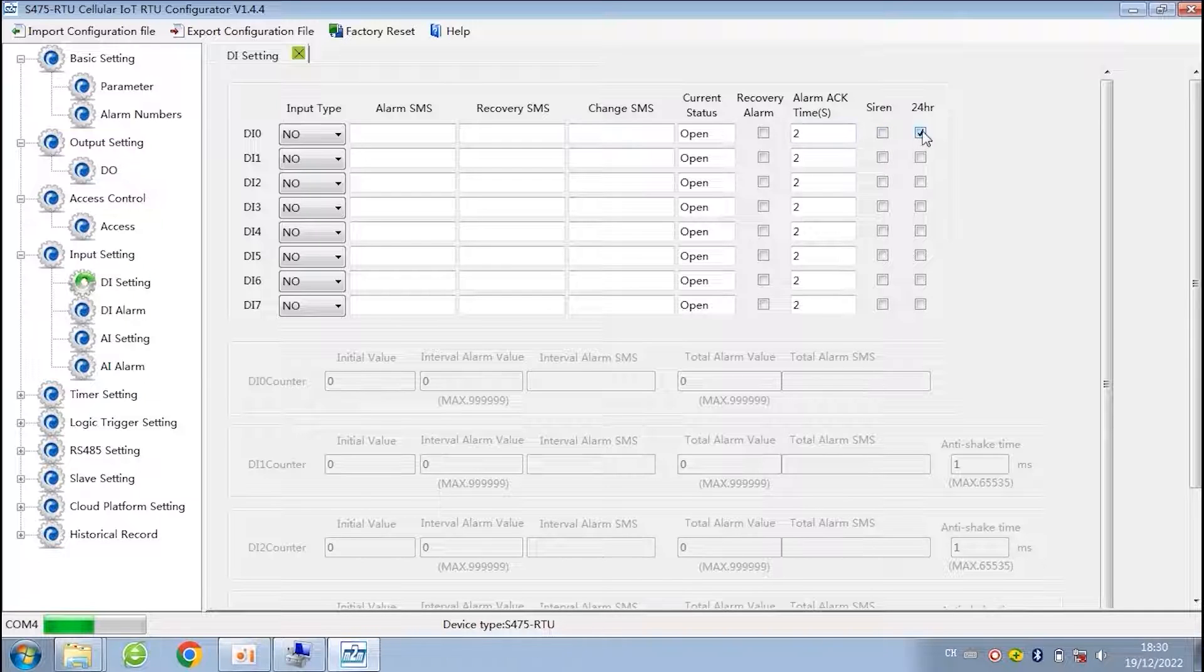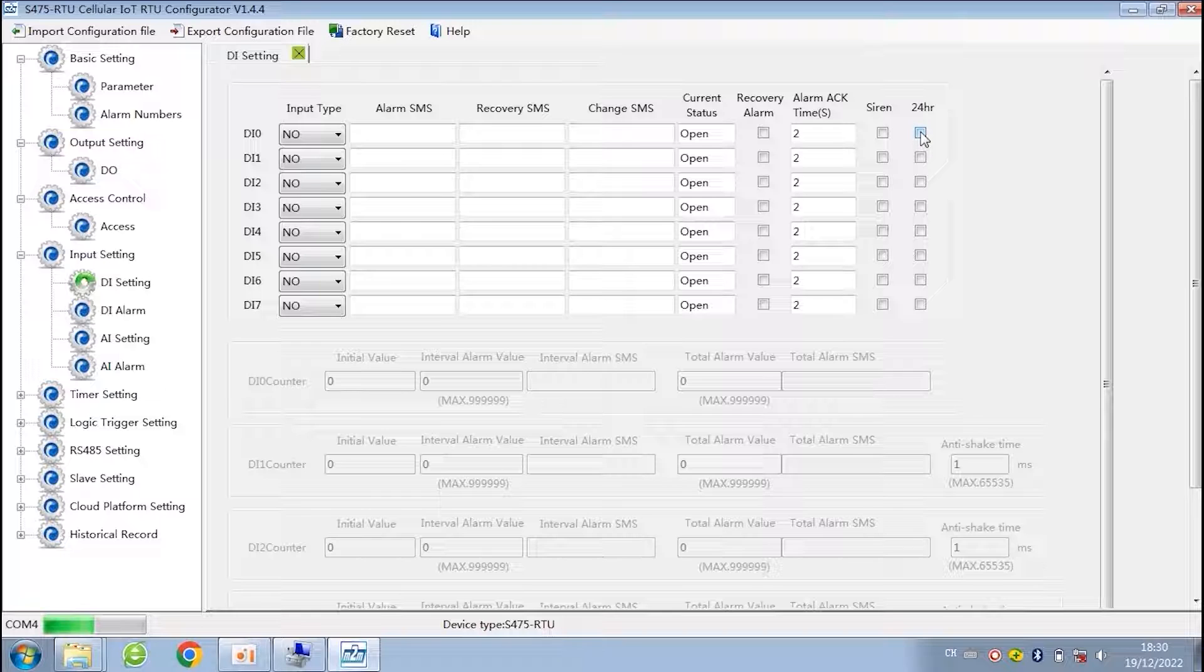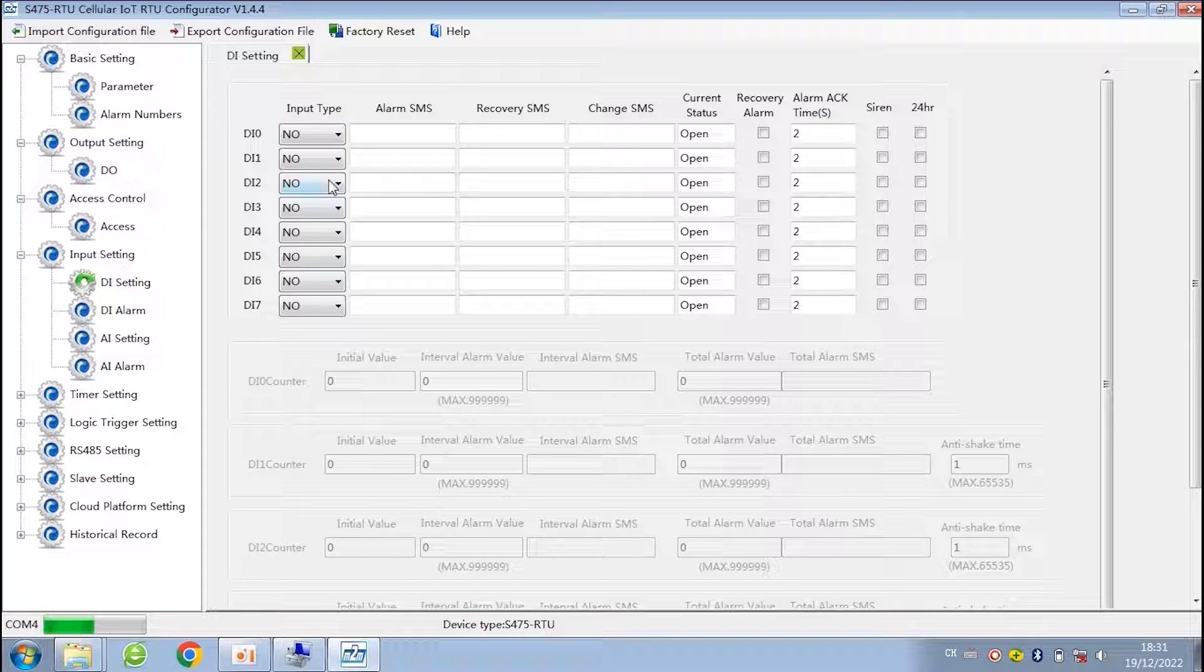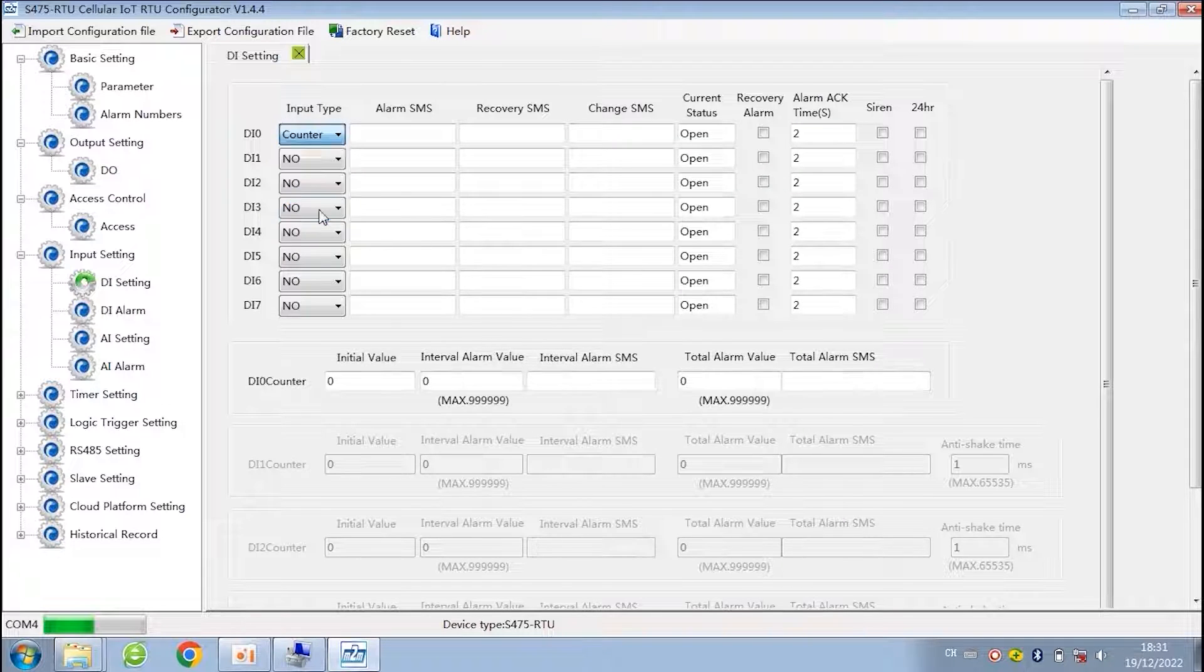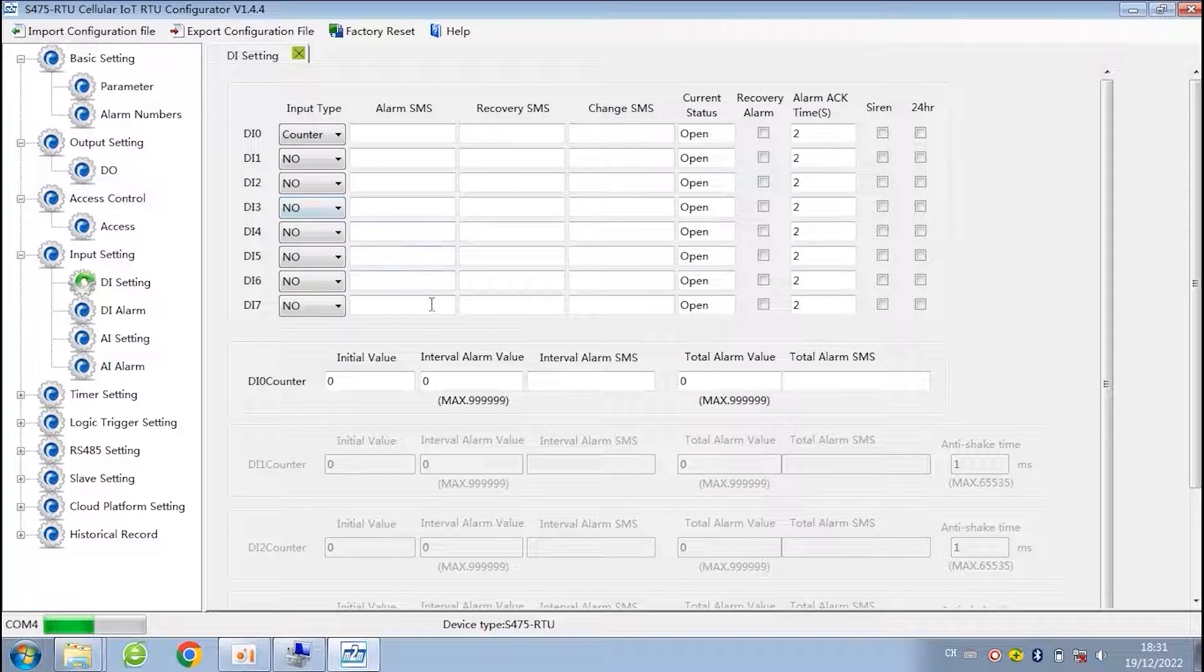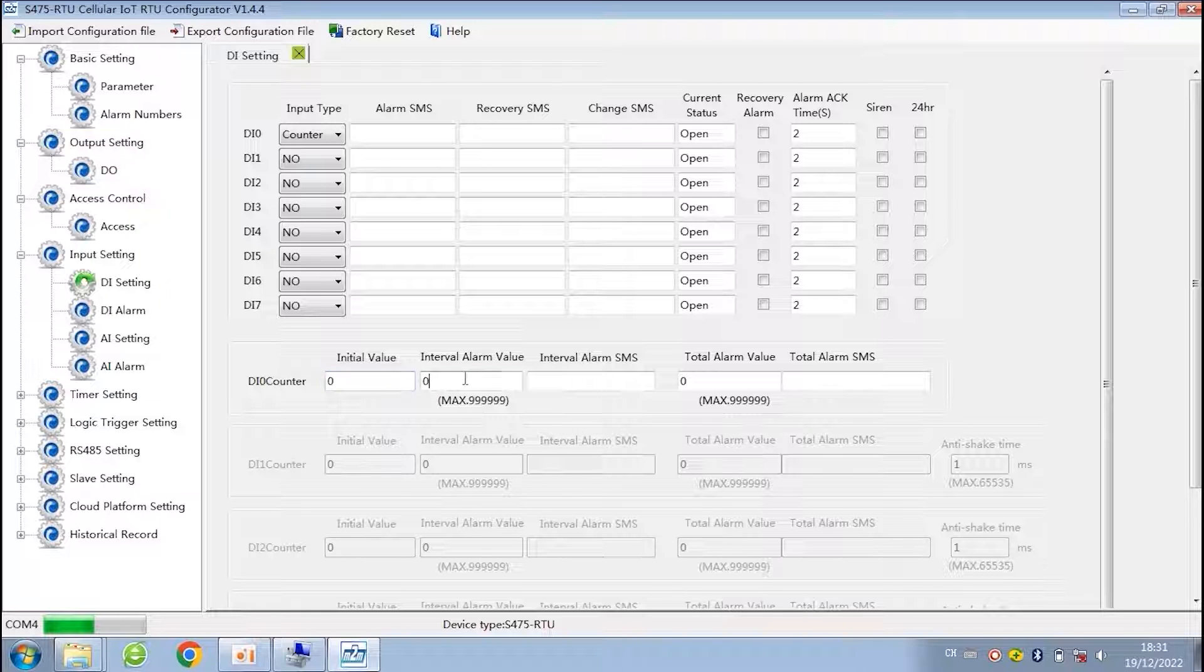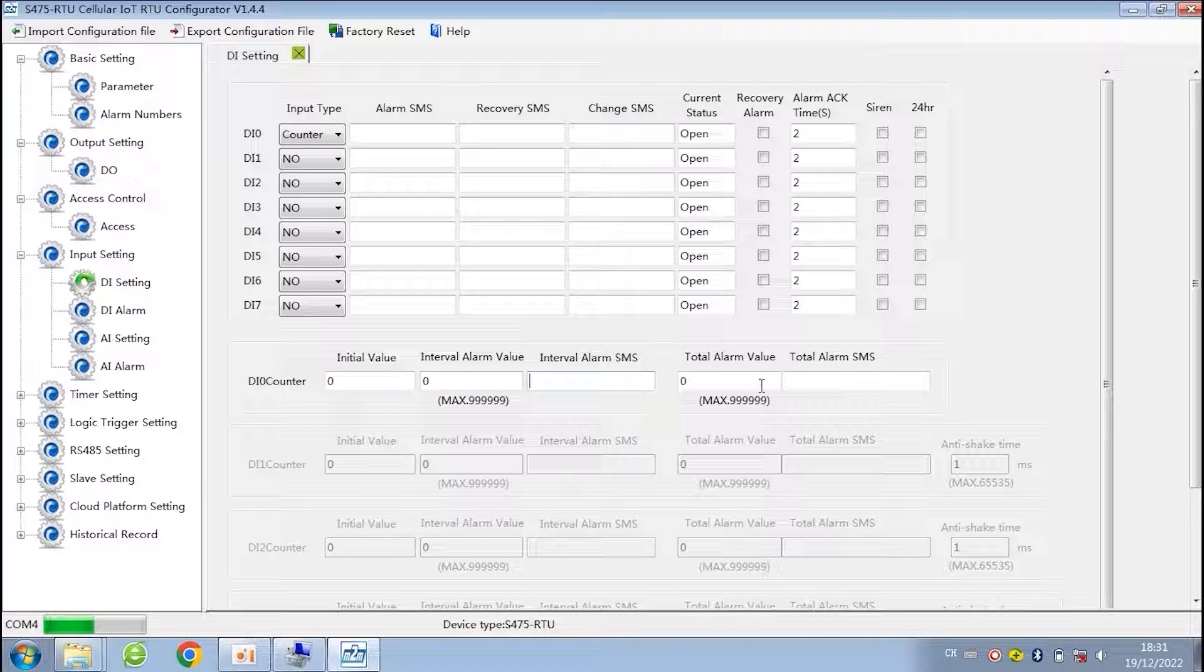The 24 hours means the RTU will send alarm no matter it is in arm or disarmed mode. If you use it as a counter, then you have to set the initial value and max value. The alarm will be triggered when the counted value reaches to the limit.